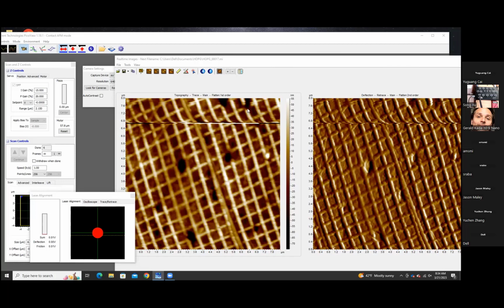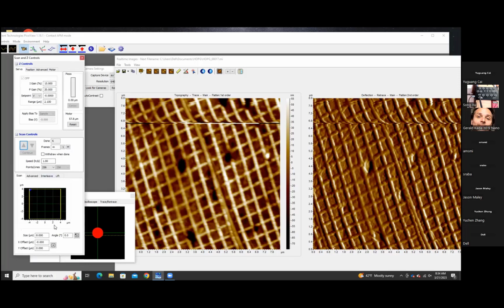So the next step is to check your high voltage supplies. So what you're going to have to do is go to your software settings. Are you in front of the PC, Song? Yes. All right, so we're going to go to the scan tab under your servo controls. Scan tab, yes. And set your scan size to 0.1. Scan size 0.1. And then make sure that you're centered on your offsets. Center. And you can just click the plus button and that will automatically center it.